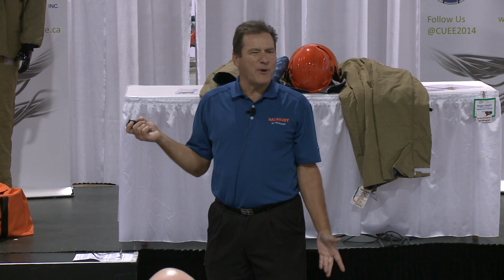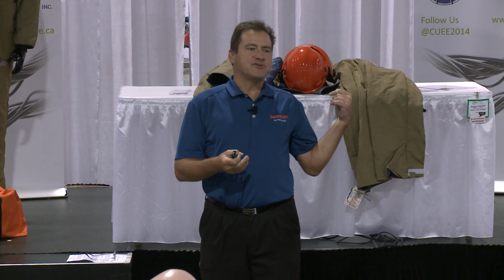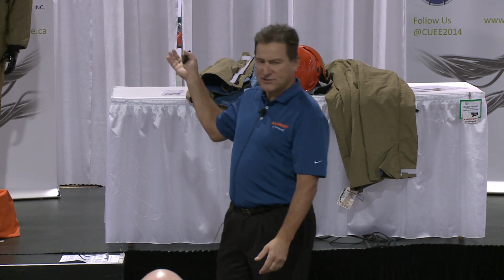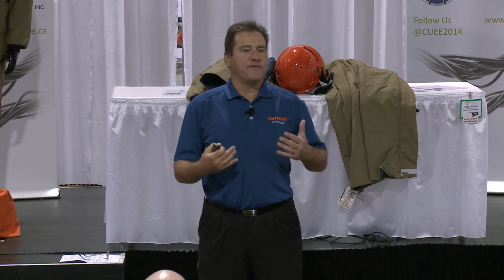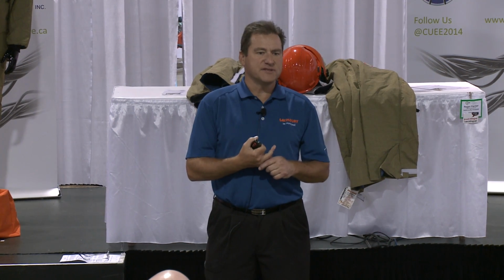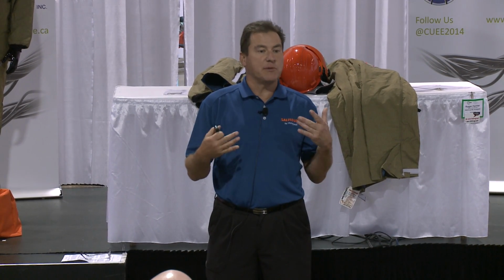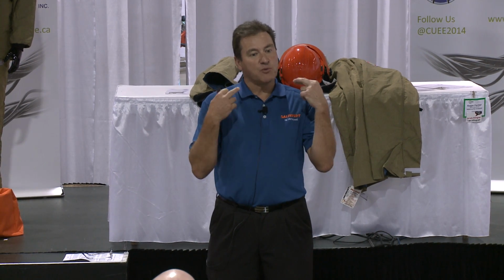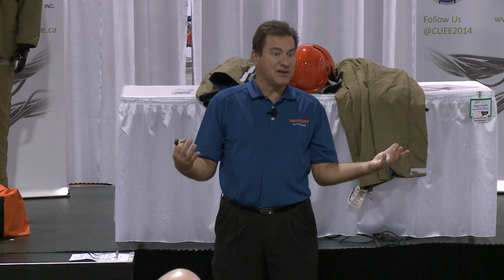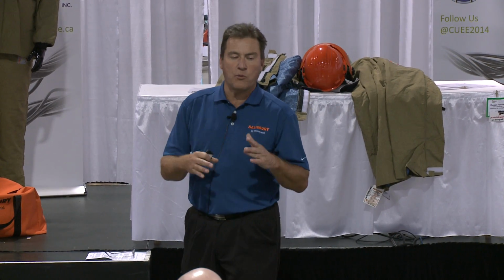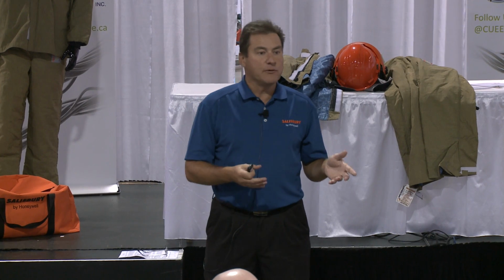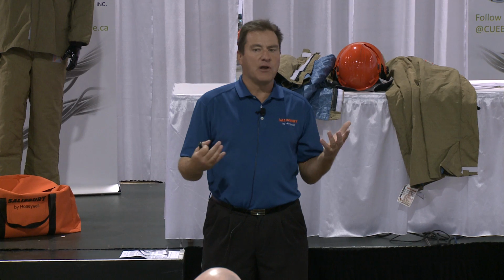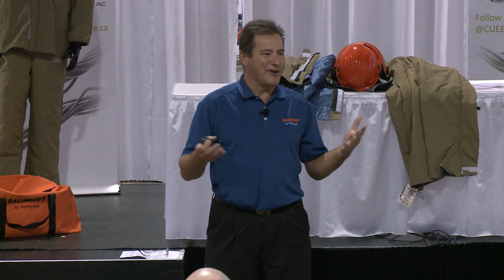You may wonder why safety glasses are included in an arc flash kit, and I'll explain that. The ASTM 2178 standard requires that you wear an arc flash rated face shield. But anytime you wear a face shield, whether in Canada or the US, there's a standard requiring that anytime you wear secondary protection, a face shield, you must also wear primary protection, safety eyewear. That's in a different regulation than arc flash, but regardless of the reason you wear a face shield, whether for welding, grinding, or arc flash, you have to wear safety glasses. Honeywell as a company is very careful about liability, like any large company is.